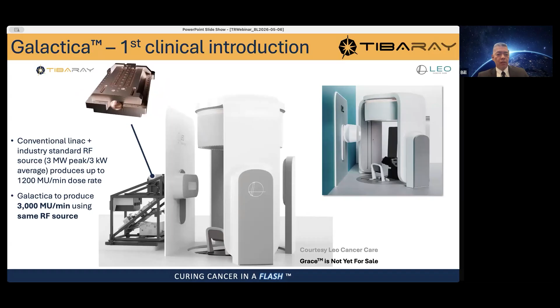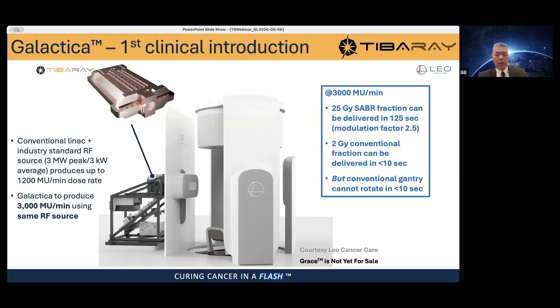A conventional LINAC using a standard RF power source would produce that 1,200 monitor unit per minute type of dose range, whereas using the Galactica, which we have partnered with Leo Cancer Care to put into their system, would give that 3,000 monitor units per minute using the same very modest amount of input power. So what that translates to clinically is that that very high dose, very focused treatment that I mentioned earlier can be delivered in just about 2 minutes, whereas a more conventional dose, smaller doses delivered daily over a few weeks, can now be delivered in under 10 seconds, which anyone can basically hold their breath for that period of time. But when you're moving the machine around the patient, you can't move it that fast. When the patient is upright and turning in a chair, you can.